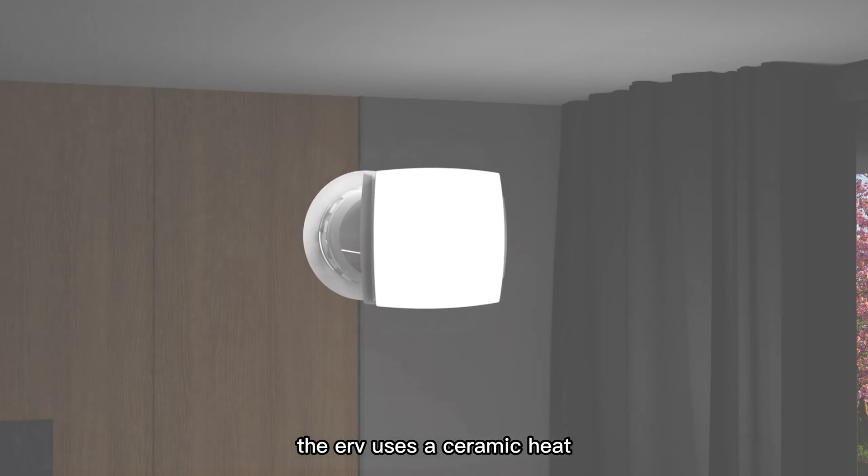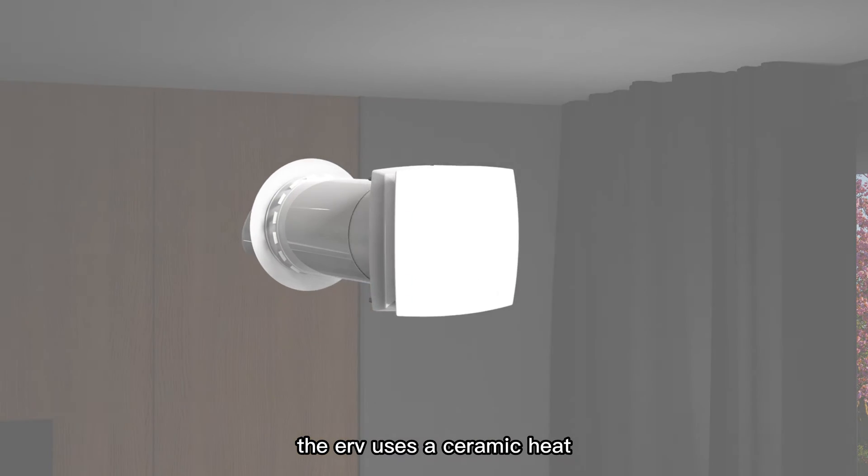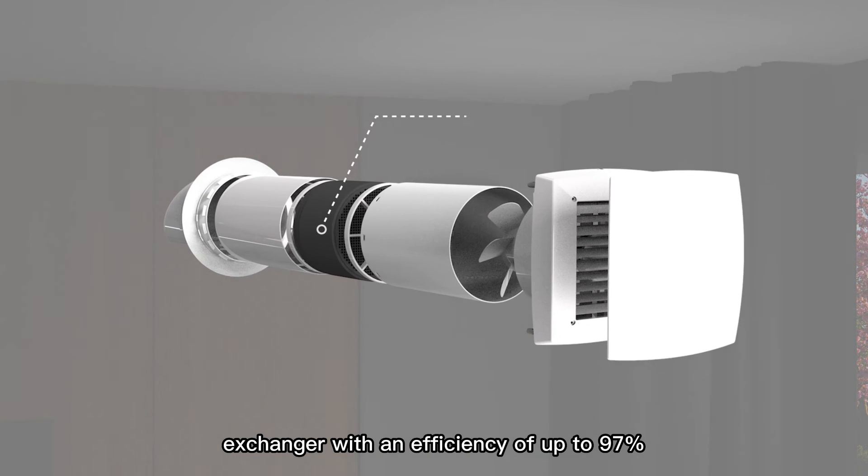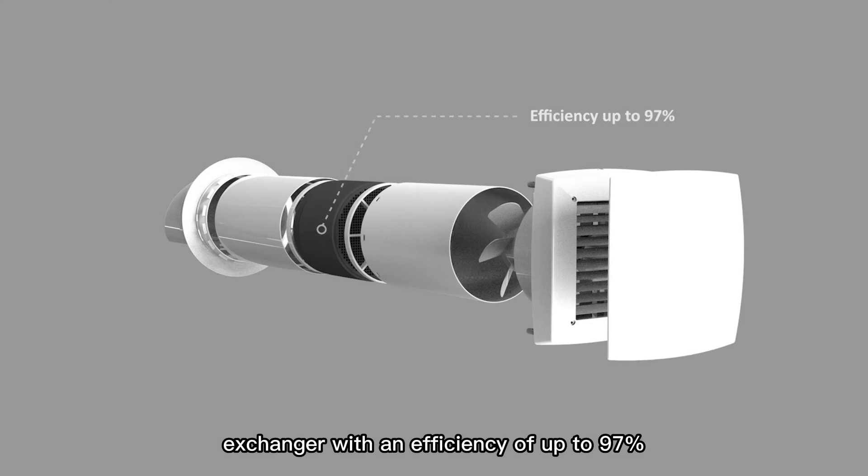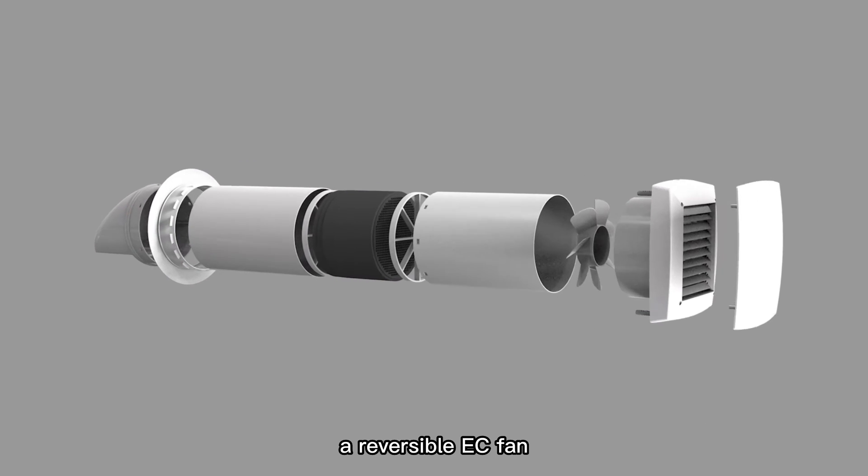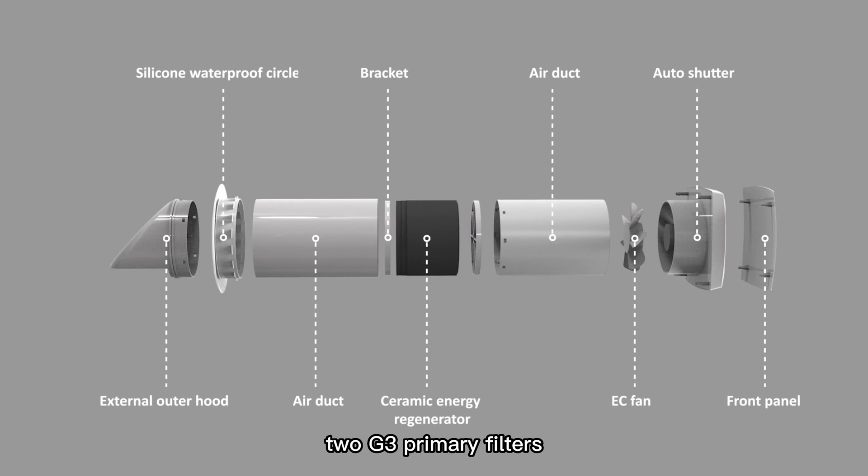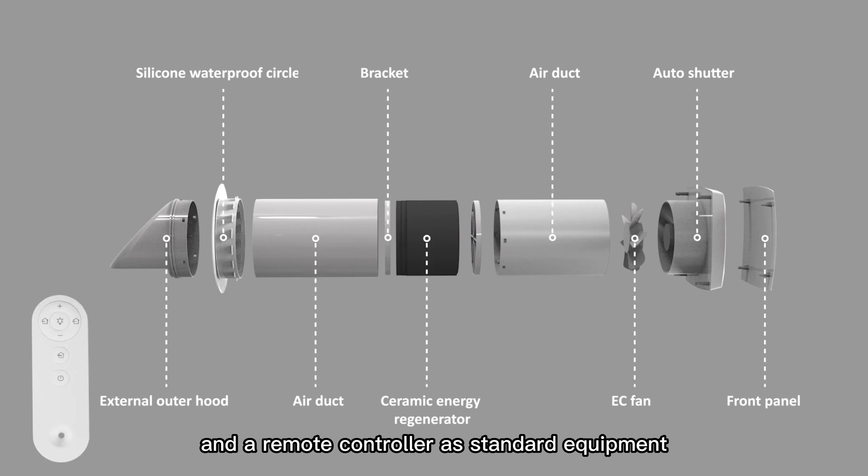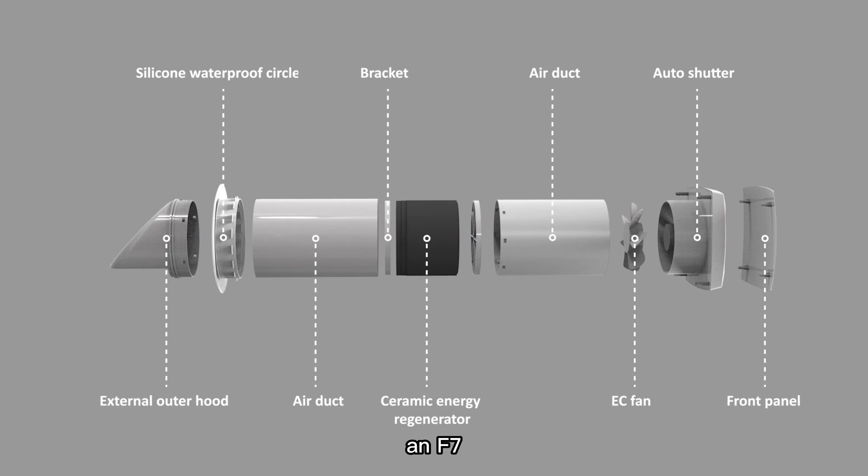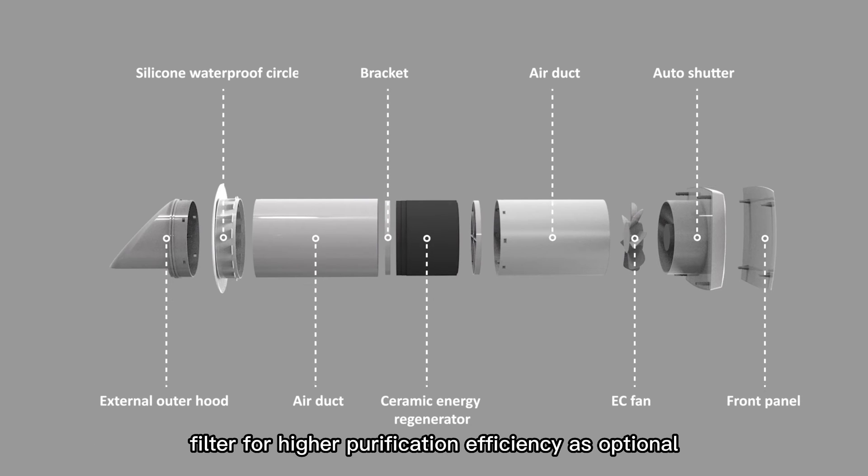The ERV uses a ceramic heat exchanger with an efficiency of up to 97%, a reversible EC fan, two G3 primary filters, and a remote controller as standard equipment. An F7 filter for higher purification efficiency is optional.